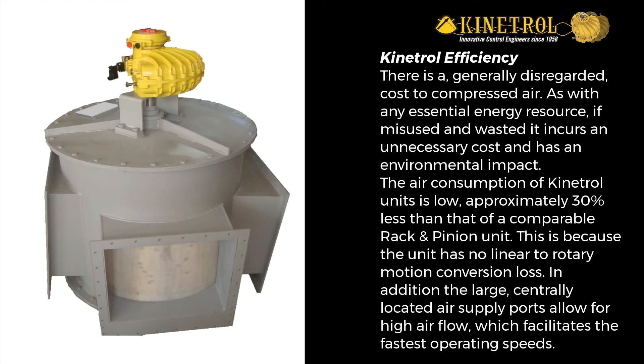Efficiency: there is a generally disregarded cost to compressed air. As with any essential energy resource, if misused and wasted it incurs an unnecessary cost and has an environmental impact. The air consumption of Kinetrol units is low — approximately 30% less than that of a comparable rack and pinion unit.